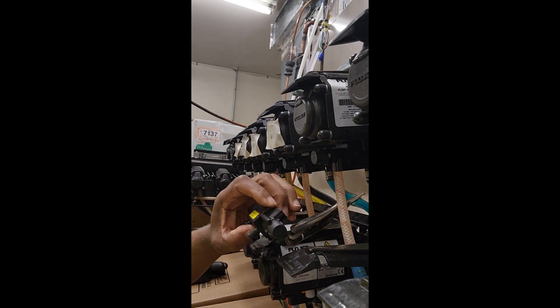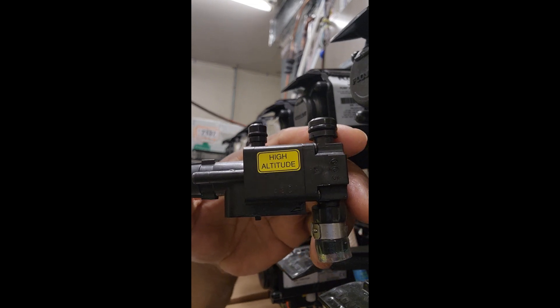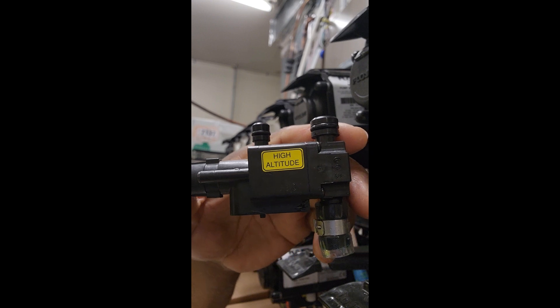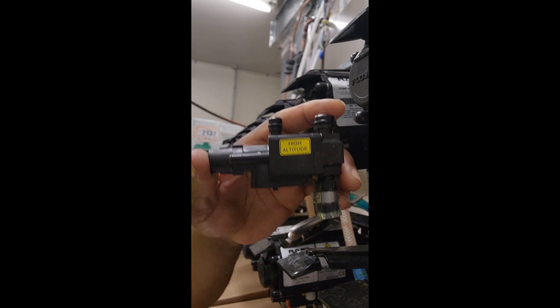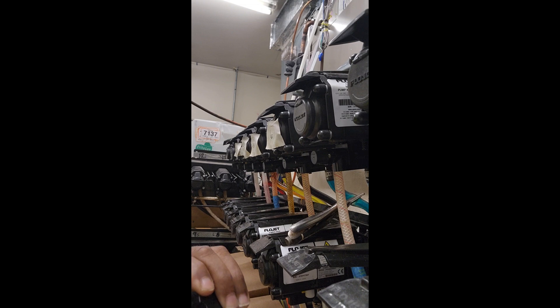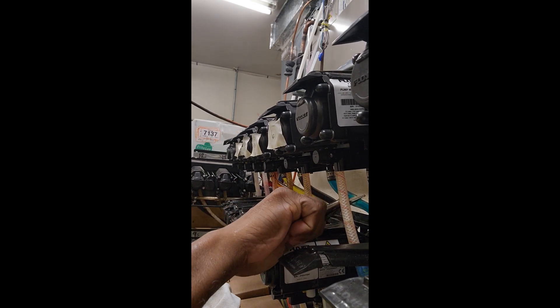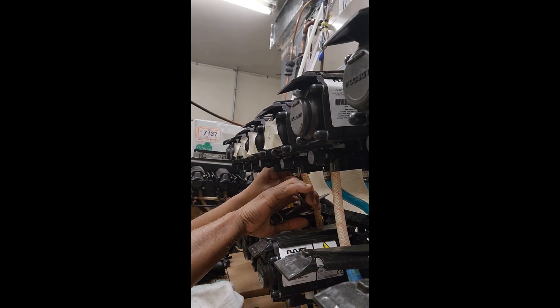These here are the high-altitude ones I'm taking off — you can see the 'high altitude' label on them. I'm going to clean these fittings off and we can probably sell these to a company that's out in the high-altitude areas, so they can make some use of them. They're brand new — they're not bad, they just don't work in this area. I've got about four more of these to do.